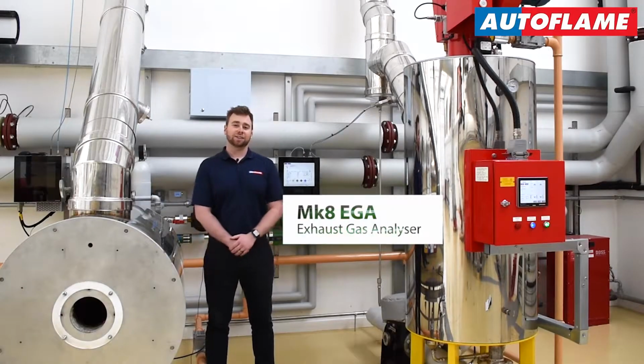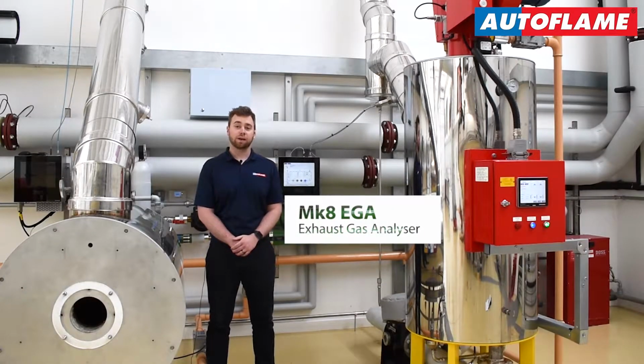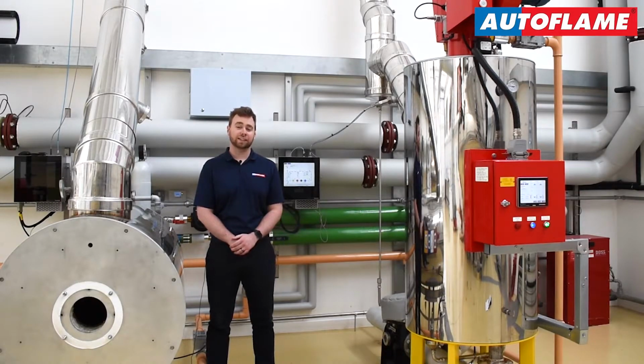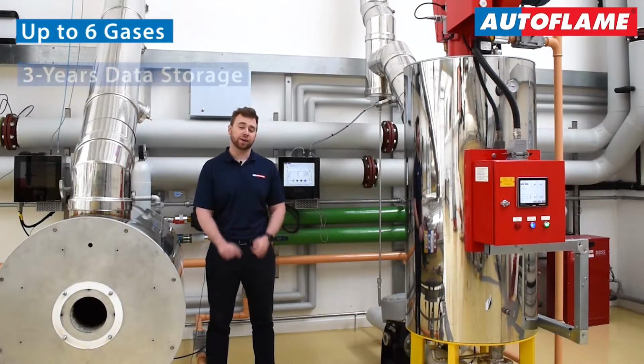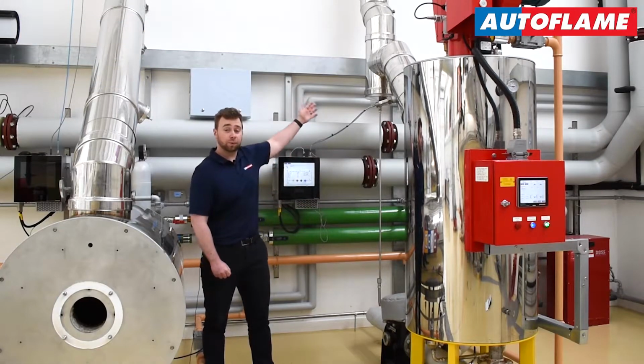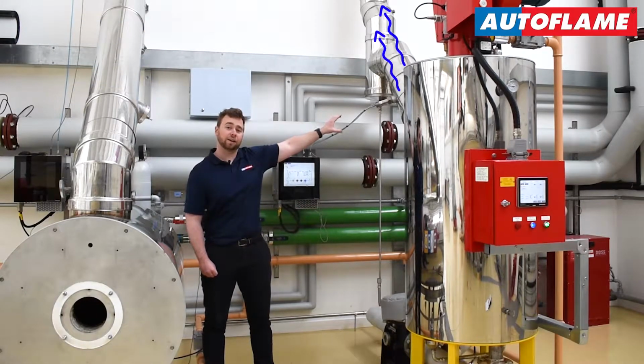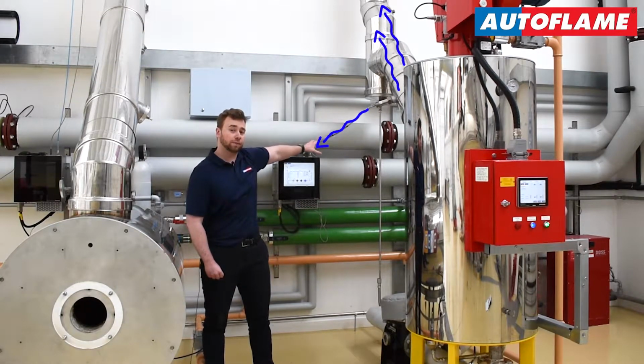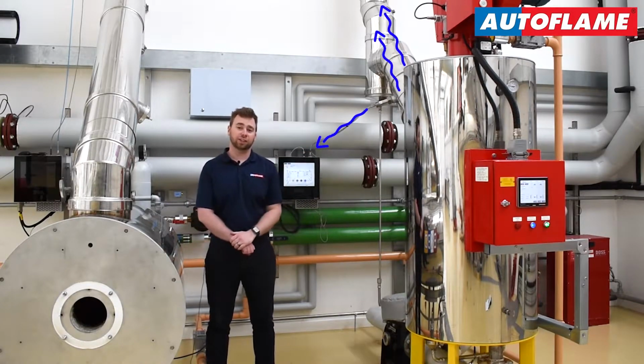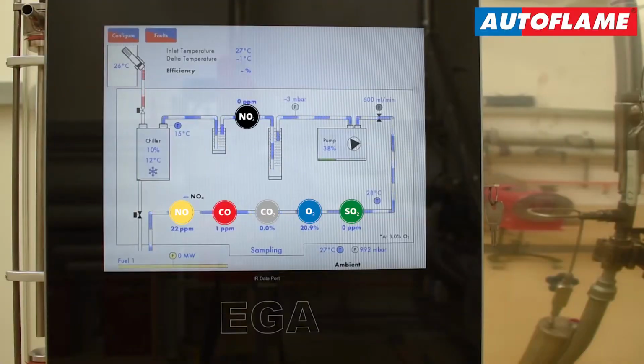The EGA is a continuous emissions monitoring system, measuring and storing emissions data of up to 6 gases for 3 years. A wet sample is extracted from the boiler stack through the sampling probe and tubing and analysed by the EGA. The EGA measures, as standard, O2, CO, CO2 and NO emissions in the flue gases. Optionally, NO2 and SO2 cells can be installed.